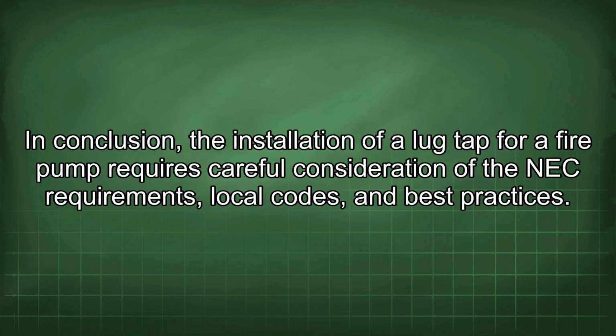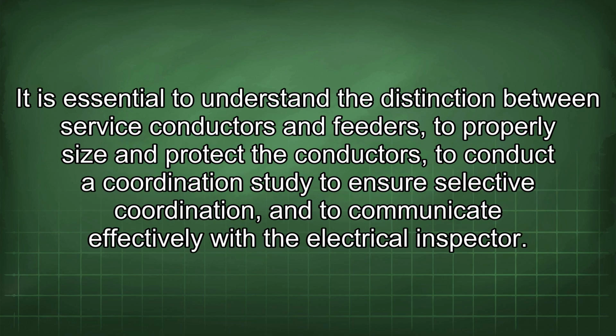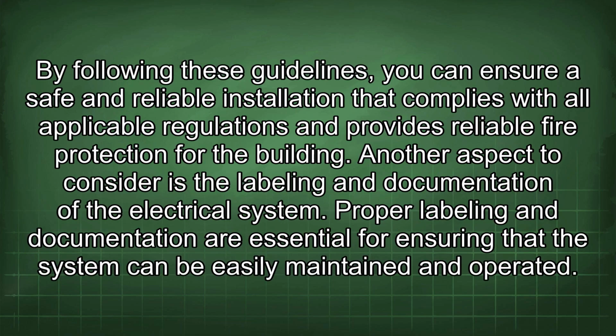In conclusion, the installation of a lug tap for a fire pump requires careful consideration of the NEC requirements, local codes, and best practices. It is essential to understand the distinction between service conductors and feeders, to properly size and protect the conductors, to conduct a coordination study to ensure selective coordination, and to communicate effectively with the electrical inspector. By following these guidelines, you can ensure a safe and reliable installation that complies with all applicable regulations and provides reliable fire protection for the building.